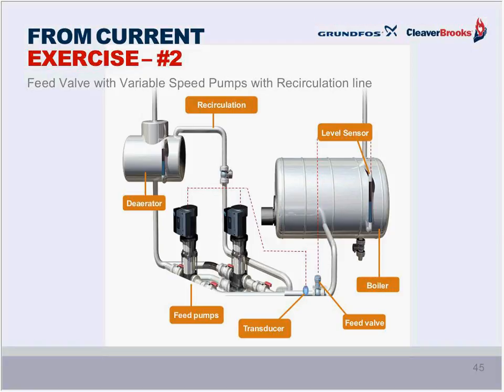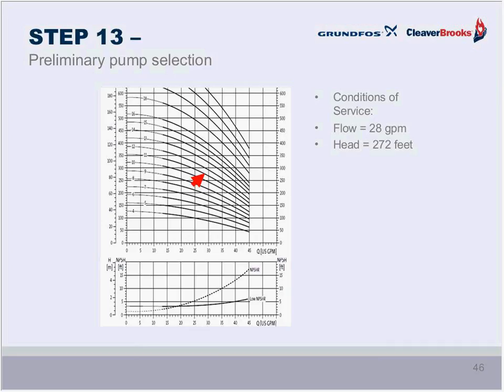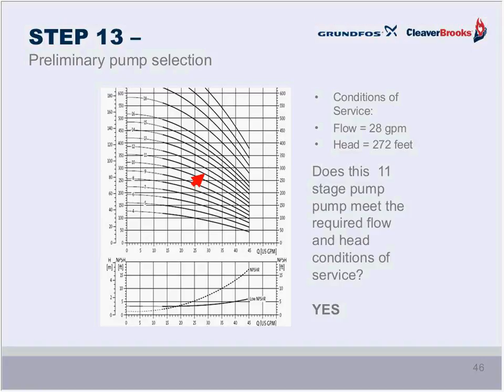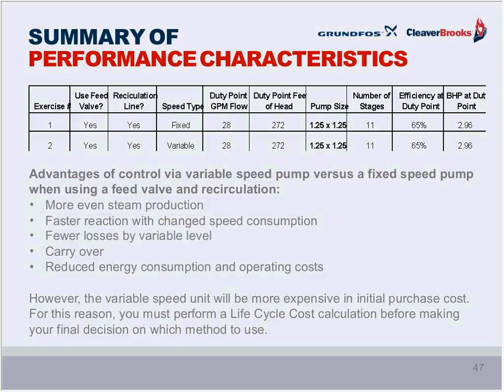So I'm going to jump through some of the steps in this, and we're going to go right to this performance curve. As in the previous exercise, this pump requires exactly the same 28 gallons at 272 feet, and we find that an 11-stage pump meets the conditions of service. And we're jumping through this exercise quickly because we're going to dwell on the next one in a little more depth. So yes, that 11-stage pump met our need. Here we can do some comparison. Exactly the same pump and motor models as used in the previous one, except this one has a variable speed drive. The previous one was for fixed speed.